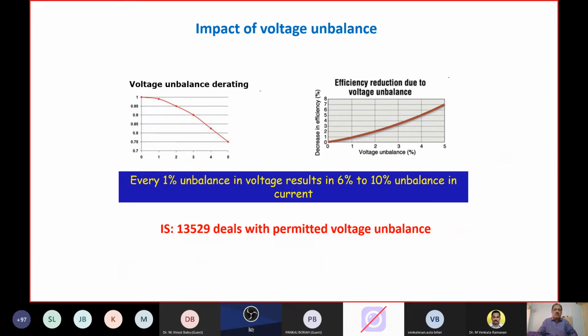We also will talk about the voltage unbalance. Voltage unbalance is not similar to voltage variation. Voltage unbalance is the unbalance in 3 phases. So as you can see here, up to 1% unbalance is permitted. The variation in current will be 6 to 10%. It is permitted by the standard. But anything more than 1%, there will be derating in the motor output, or the efficiency will reduce as the unbalance increases. So as you can appreciate, the unbalance in voltage is also undesirable.